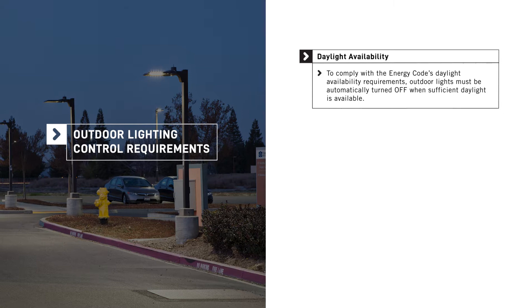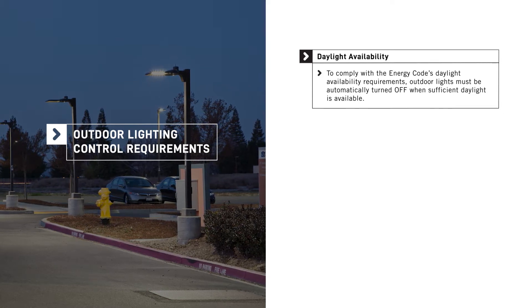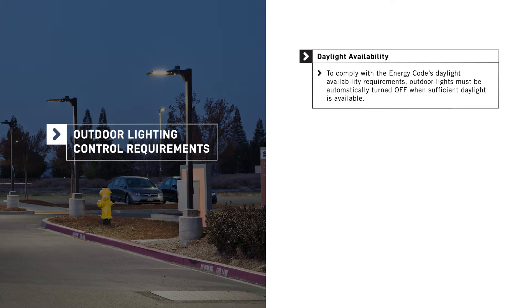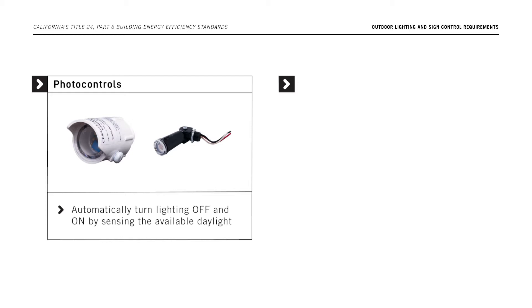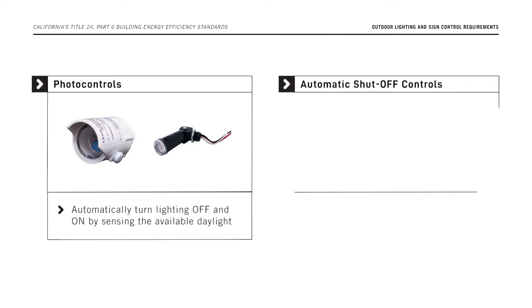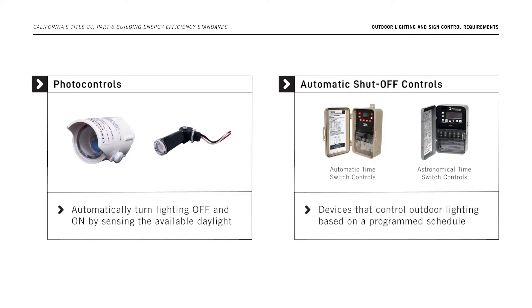To comply with the Energy Code's Daylight Availability requirements, outdoor lights must be automatically turned off when sufficient daylight is available. Two types of lighting controls that meet this are: one, a photo control, which automatically turns lighting off and on by sensing the available daylight; and two, an automatic shut-off control, which controls outdoor lighting based on a programmed schedule. One type of automatic shut-off control, called an astronomical time switch, includes a feature that adjusts the programmed schedule according to local sunrise and sunset times.